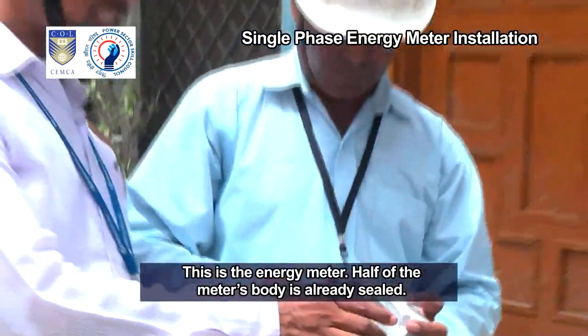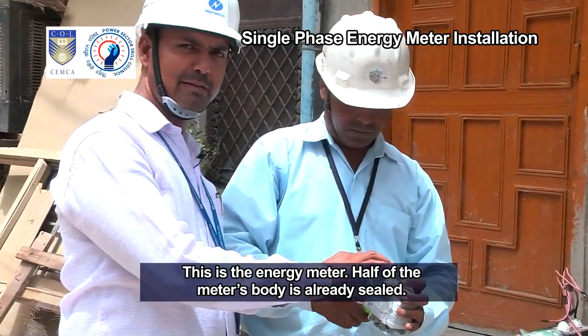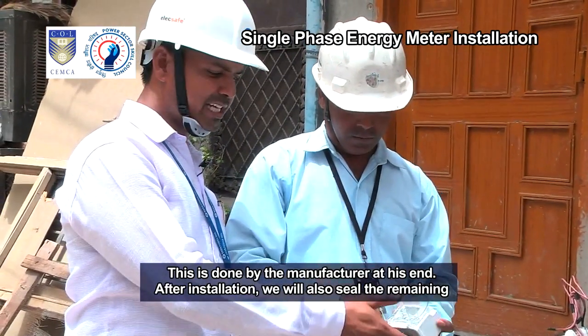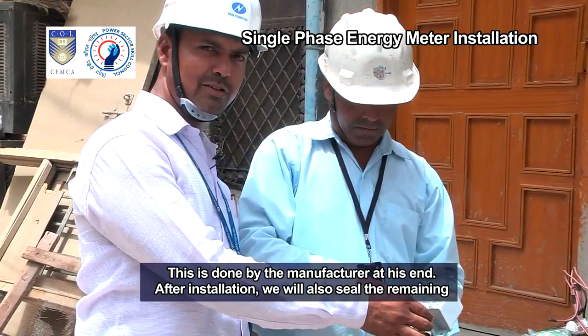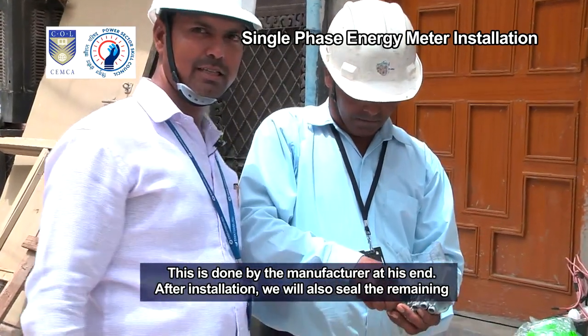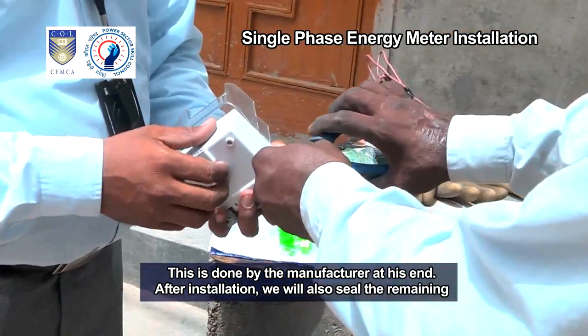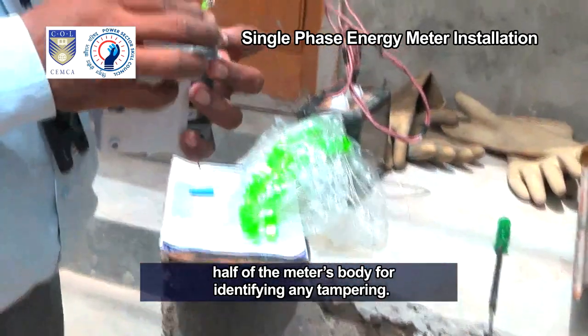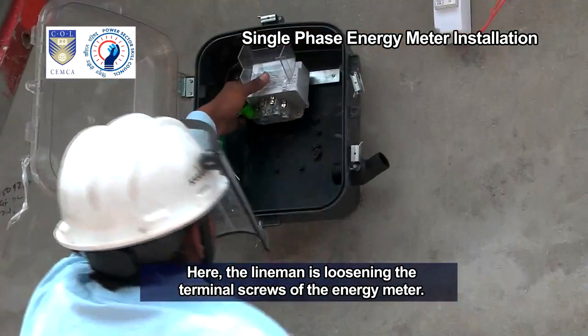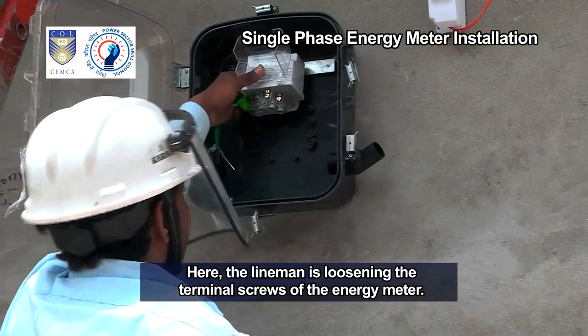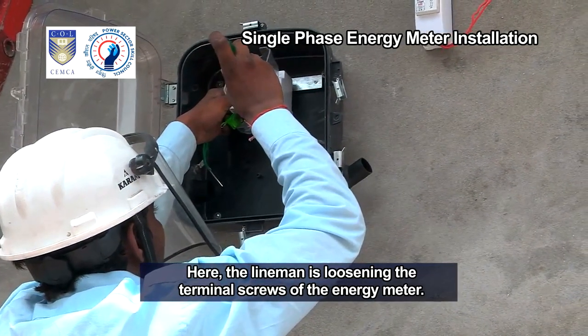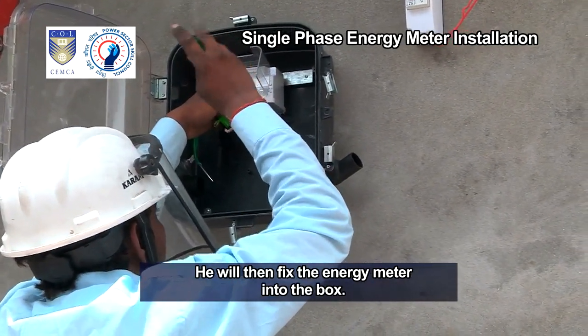This is the energy meter. Half of the meter's body is already sealed. This is done by the manufacturer at his end. After installation, we will also seal the remaining half of the meter's body for identifying any tampering. Here, the lineman is loosening the terminal screws of the energy meter. He will then fix the energy meter into the box.